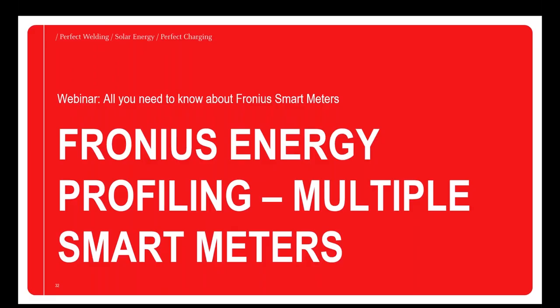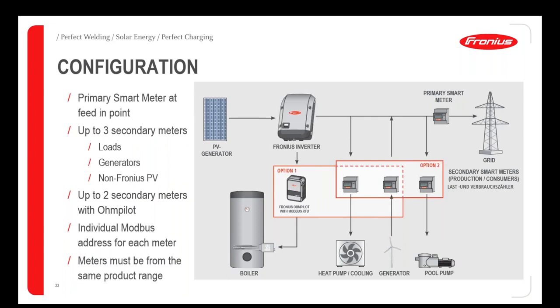You can also add multiple smart meters onto the same site. So this can be a benefit for customers who want to see certain loads. You might have very high loads for something like a pool pump or a heating system. You might have an EV charger that you want to integrate into your SolarWeb page. Also, you can add your additional generators, so things like your wind turbine or some non-Fronius inverters. That can all be incorporated into SolarWeb by adding additional smart meters. And of course, being a lower cost unit, the TS100 makes a lot of sense to be used in line for each of those individual devices.